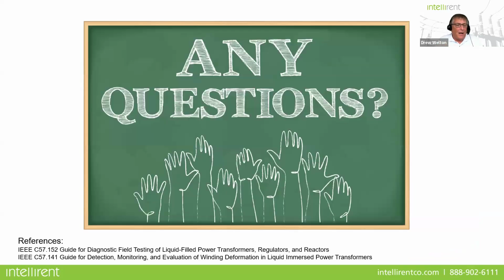Okay. Just a couple of references: C57-152, Guide for Diagnostic Field Testing of Power Transformers; C57-141, Guide for Detection, Monitoring, and Evaluation of Winding Deformation. There's also a new guide out for monitoring systems from IEEE, and the field testing guide has also been updated and is due to be released soon. And Farad will talk about vibroacoustic testing of LTCs, and that's also contained in the new IEEE guide for field testing of oil filled transformers. So the resources are out there, people. I encourage you to use them and implement them into your maintenance programs.